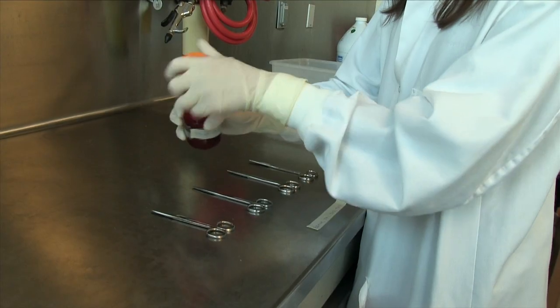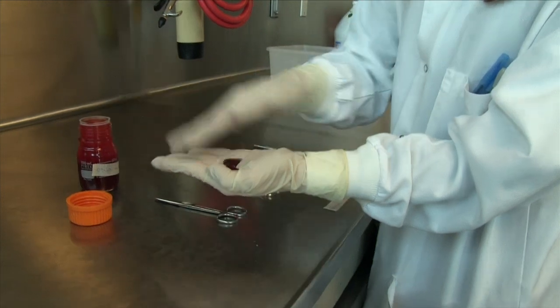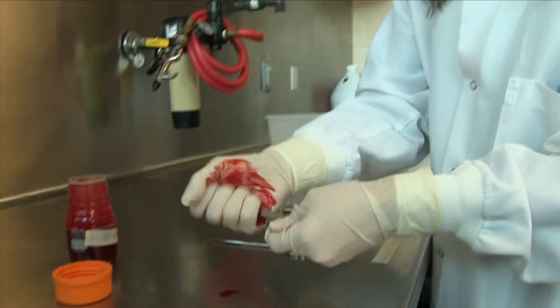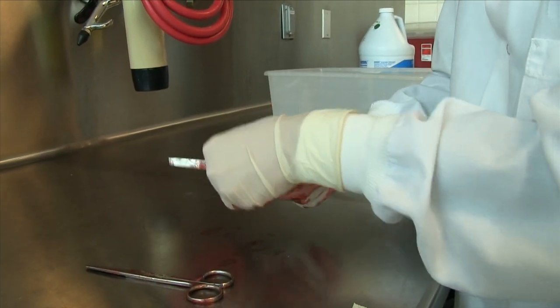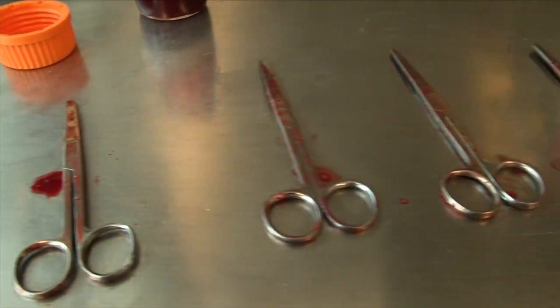Another area of focus for the FDA is the test soil that is being applied to the device for these cleaning validations. There are a number of validated, commonly used test soils. However, the FDA wants the manufacturer to make sure that the test soil that they are choosing and using for these validations is clinically relevant. For example, if the device will see blood or mucus, then the FDA wants to see a clinically relevant soil that has those constituents in it. They also want to make sure that the amount, the volume of those constituents is appropriate as far as what the device will see in the clinical setting.